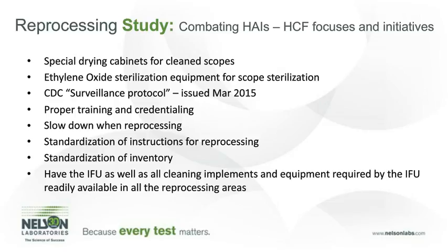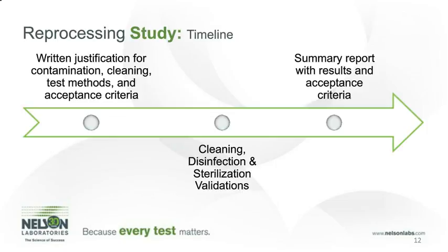It is also important to follow the standardized instructions for reprocessing and to have standardized inventory to ensure that the reprocessing instructions are appropriate and easy to follow. The reprocessing study timeline starts with a very in-depth written justification for the contamination, cleaning, test methods, and acceptance criteria of the validations that need to be performed. Next, the cleaning, disinfection, and sterilization validations are performed, and then a summary report is written with all of the results and the acceptance criteria, showing that the acceptance criteria were met. We find that the majority of questions asked by FDA are not due to incorrect testing, but incomplete justification.